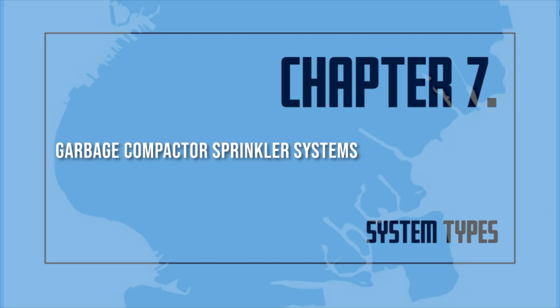The buildup of trash in the compactor chute is a fire hazard. Fires may be started in several ways, for example, by a smoldering cigarette thrown into the compactor chute. Sprinkler systems must be installed to put out fires that start in the compactor chute. Any of the standard water supply sources may be used to supply the compactor sprinkler system. For example, gravity tanks, fire pumps, and pressure tanks are all used as water supply sources.